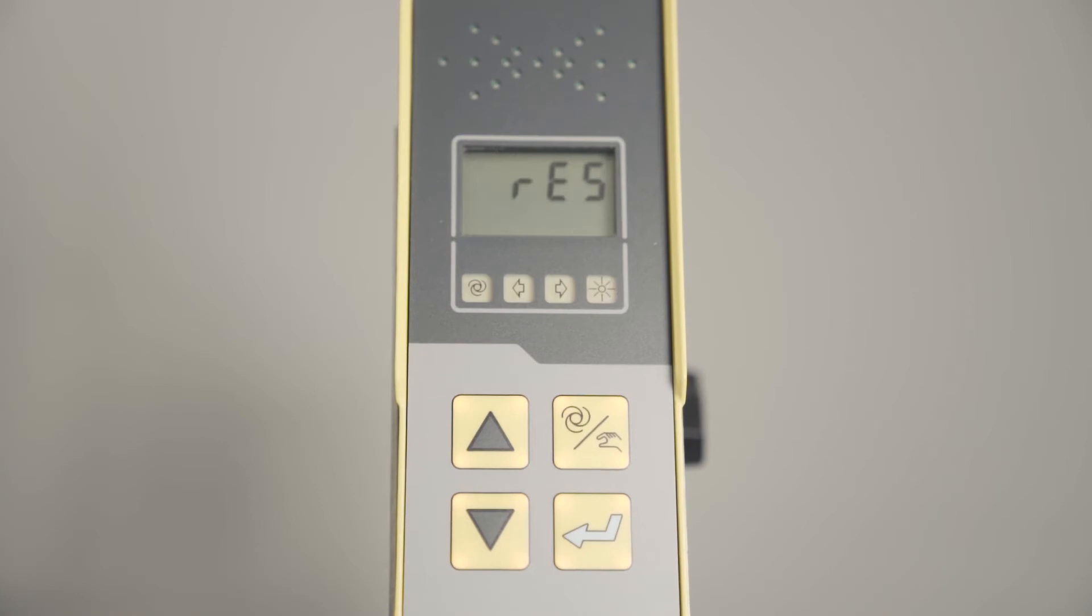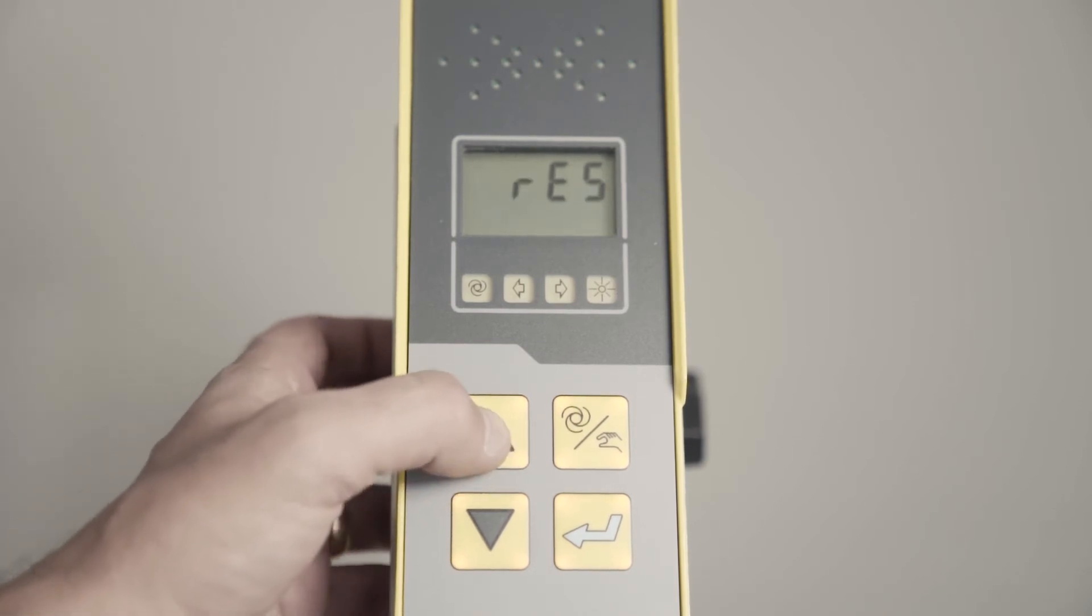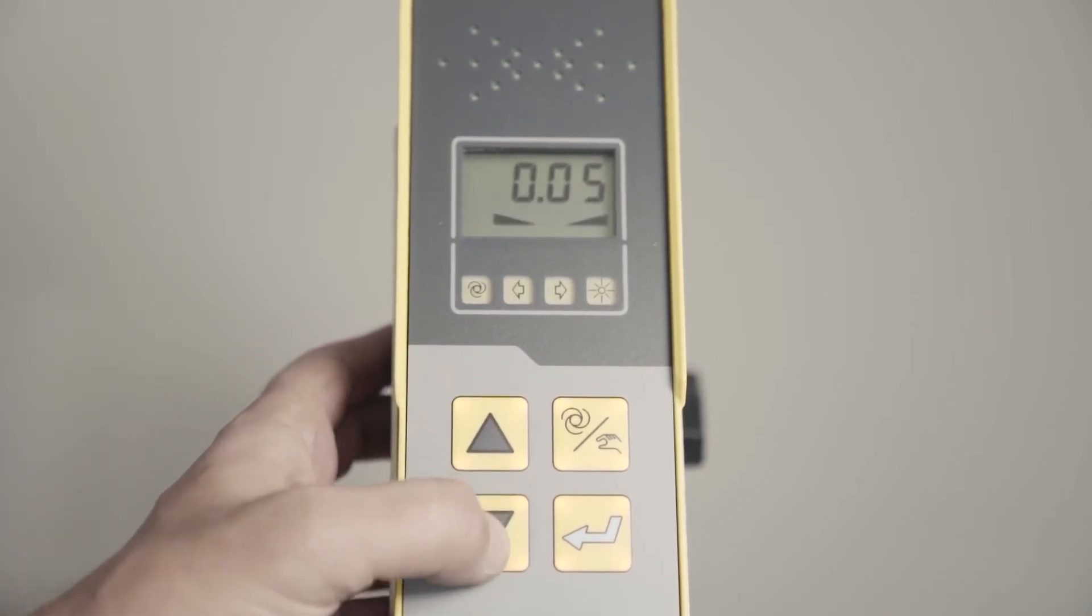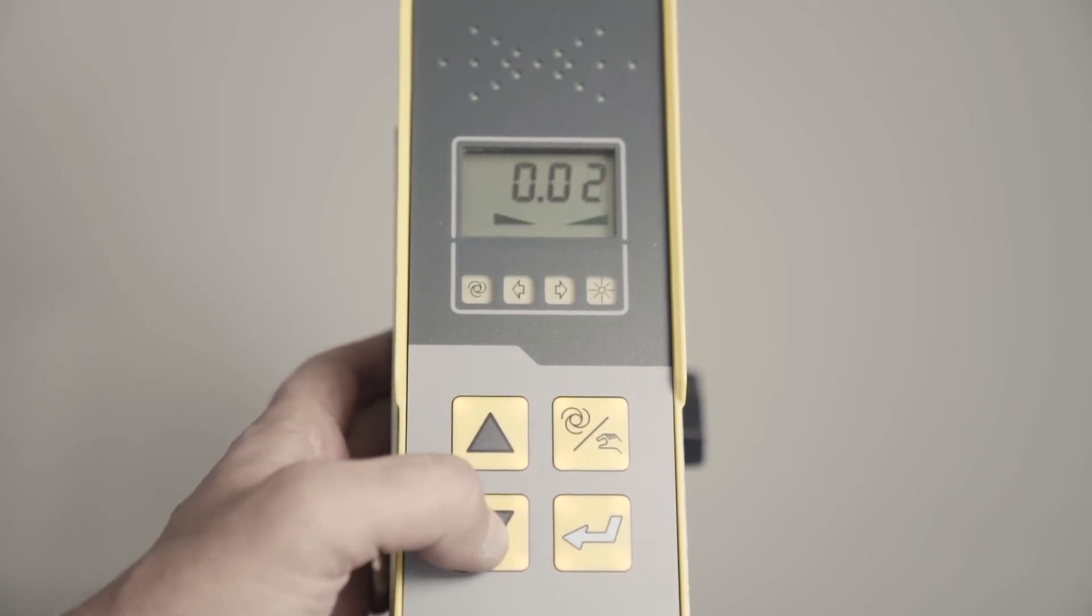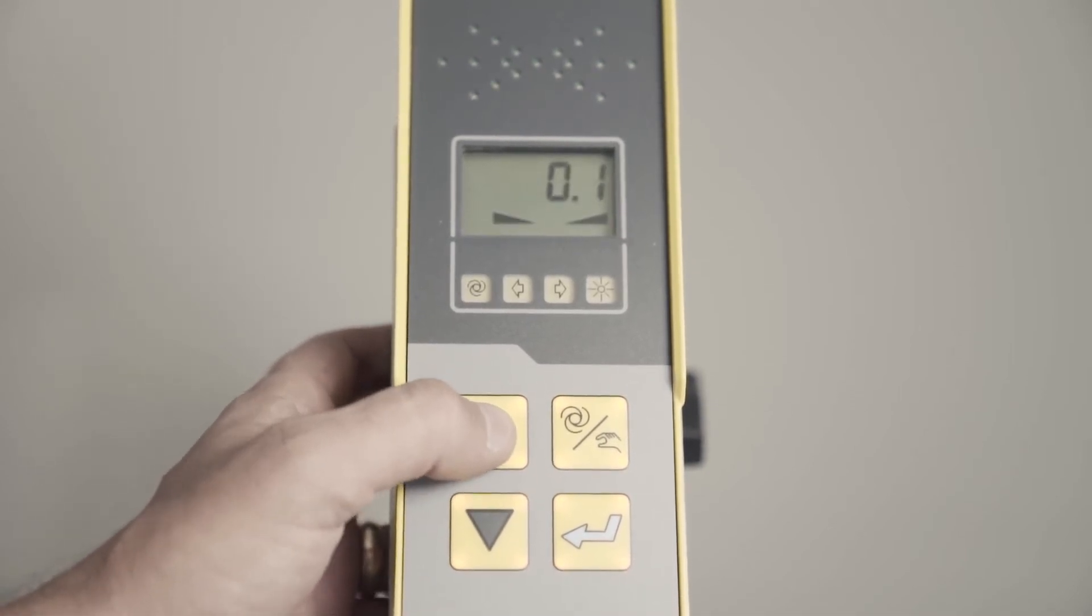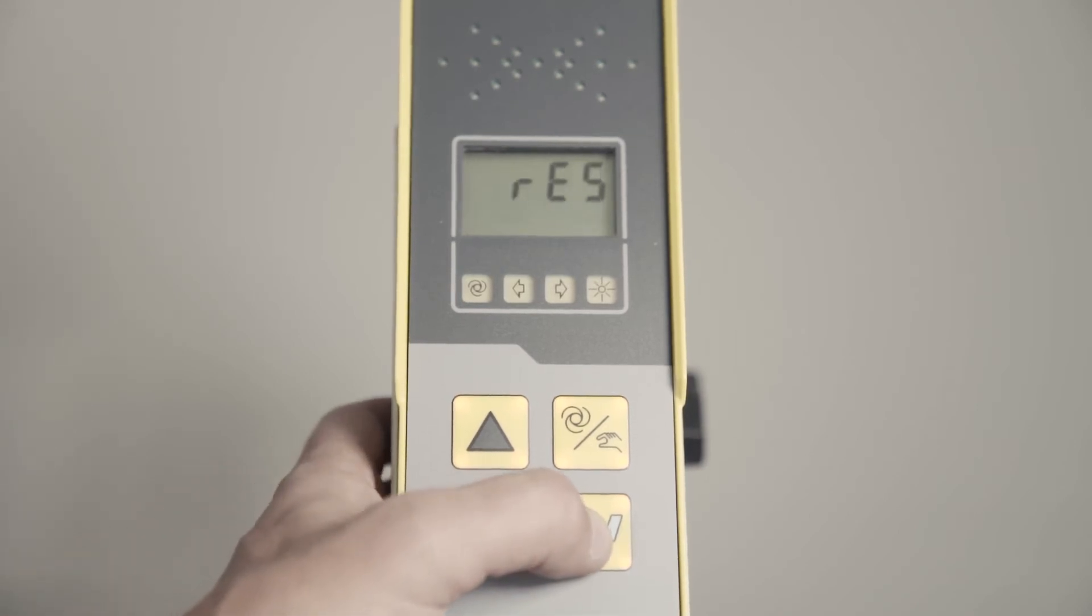Our resolution, that's how your slope sensor is going to read out. Do you want it in tenths? Do you want it in five-hundredths? Two-hundredths? Typically I'll leave it in tenths so it's not so reactive. Your numbers aren't constantly moving, but feel free to put it wherever you want.